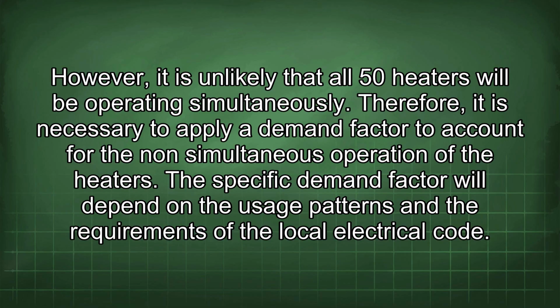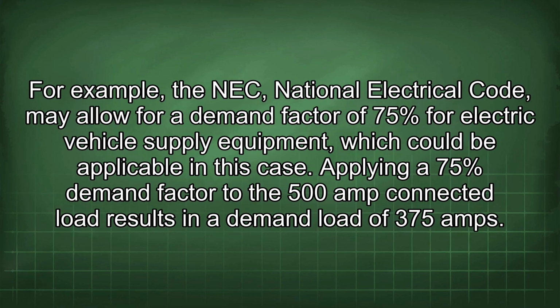However, it is unlikely that all 50 heaters will be operating simultaneously. Therefore, it is necessary to apply a demand factor to account for the non-simultaneous operation of the heaters. The specific demand factor will depend on the usage patterns and the requirements of the local electrical code. For example, the NEC (National Electrical Code) may allow for a demand factor of 75% for electric vehicle supply equipment, which could be applicable in this case. Applying a 75% demand factor to the 500 amp connected load results in a demand load of 375 amps.